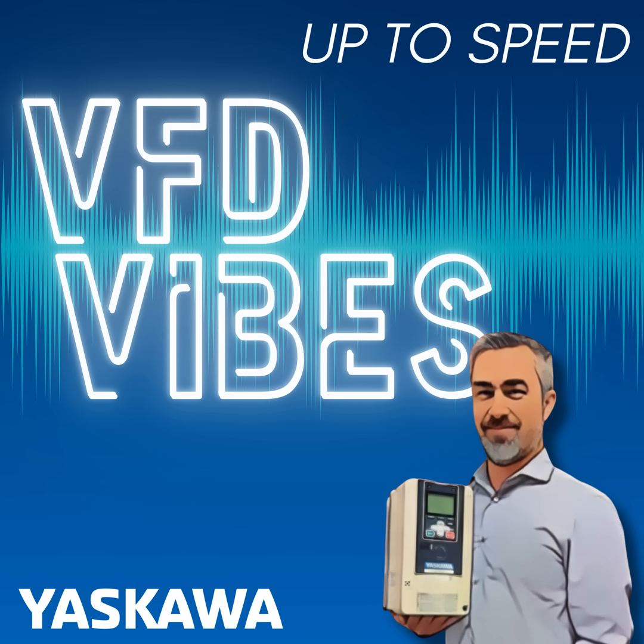Yeah, absolutely, Greg. You make a couple of good points. The first point that you made was, well, there's a number of loads, a number of devices that we connect to our power supply, which are nonlinear in nature. And as technology has evolved, you may hear the term switching power supply. It's an efficient design of a power supply. But one consequence is that switching power supplies don't draw linear current, and as a result, contribute to the formation of harmonic currents in our electrical distribution network.